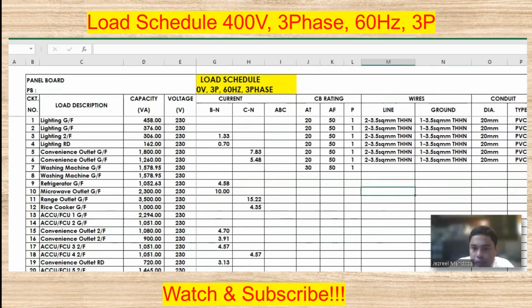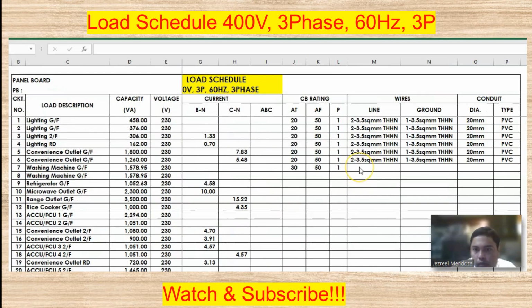And then yung size ng wire niya, we have two 5.5 square mm THHN, and then plus isang 5.5 that is for ground, and then for conduit we use the 25 mm PVC.